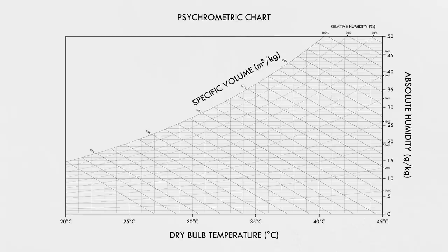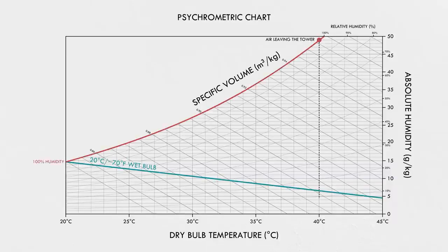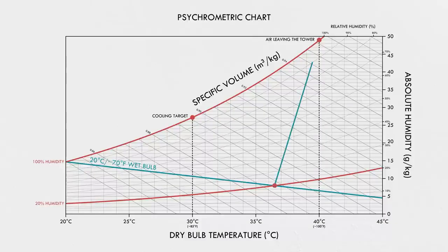Let's look back at that psychrometric chart. Say we're in an area with a wet bulb temperature of 20 Celsius, 70 Fahrenheit. The water from our condenser comes in at 40 C, 100 F, so the air leaving the tower will be saturated at that temperature, and we're trying to cool the water down to 30°C, 85°F. If the ambient relative humidity is, say, 20%, our air is starting out here and going here.